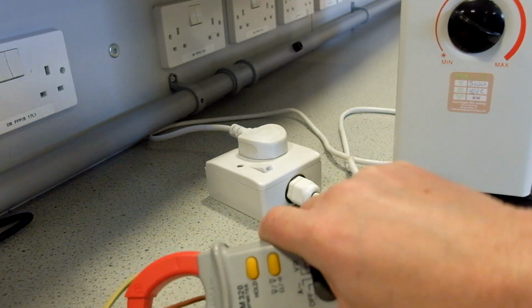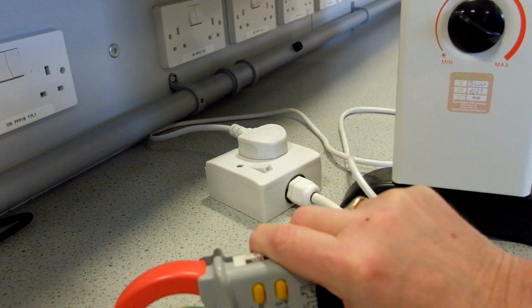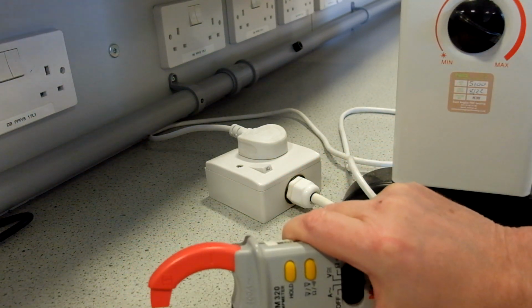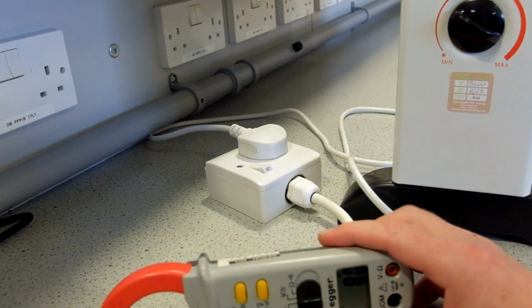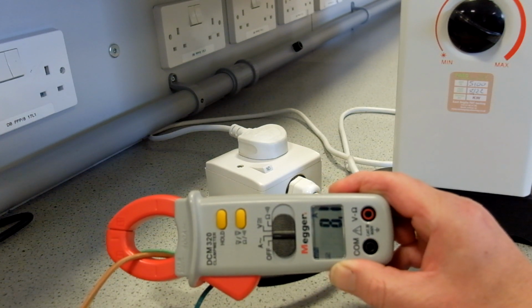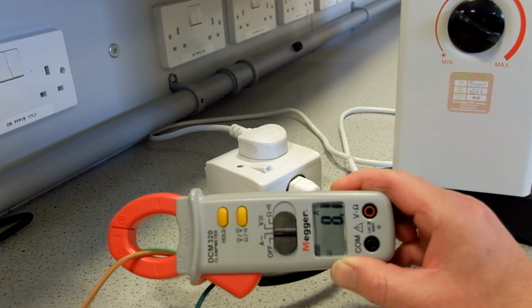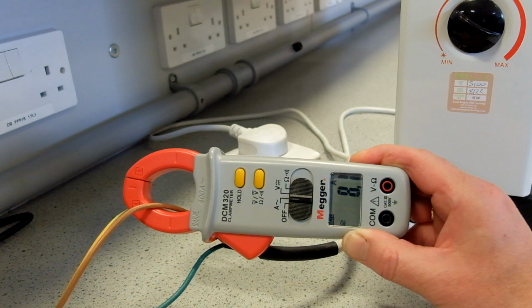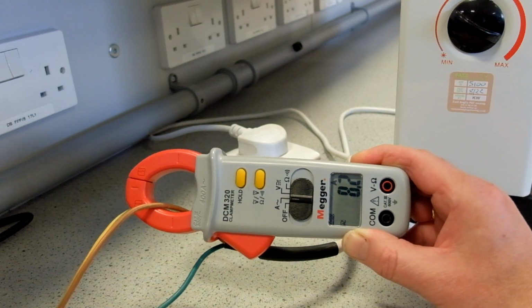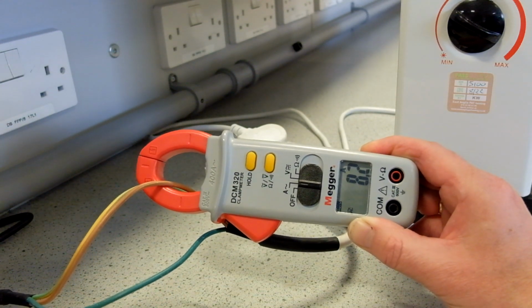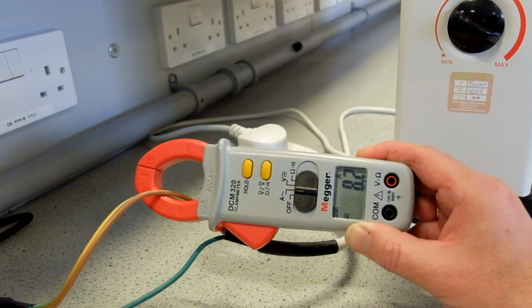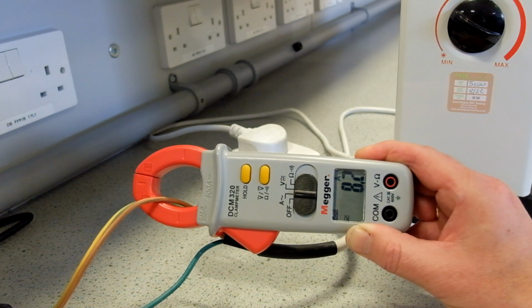the magnetic fields cancel. Again, if we go back to individual wires, we go back to the brown live, we clamp it round the cable, and we're measuring 8.1 amps. So the cable going through the live and the cable going through the neutral are the same if there is no fault current. So this clamp meter is a current transformer.